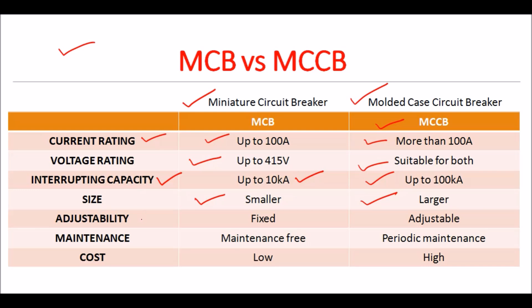Regarding adjustability, MCB has a fixed trip setting — the trip current and characteristics cannot be adjusted. Whereas in MCCB, settings can be adjusted to match specific application requirements. So MCCB is adjustable.